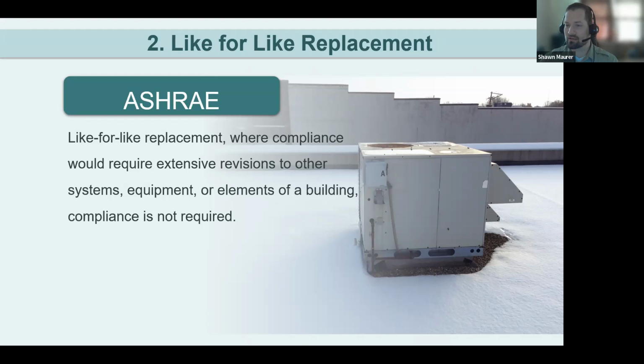Something to be aware of, like we touched on before, many systems have excess capacity. We've covered that in previous presentations. When the opportunity arises for like replacement, sizing that replacement equipment closer to the required load may also reduce some of the additional requirements that may otherwise be required for the original size system. So when you're looking at the IECC, some system components like economizers or heat recovery ventilation are based on the size of the equipment. And so if you can downsize the equipment, you can simplify those controls. That's an advantage the IECC has, that it mandates proper sizing, where ASHRAE can allow you to put in the same size equipment. You kind of miss out on that opportunity to simplify your system a little bit.